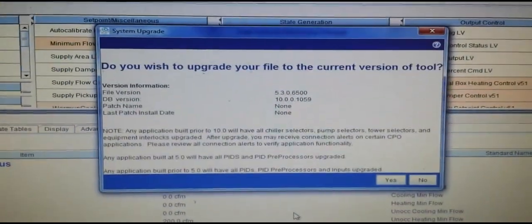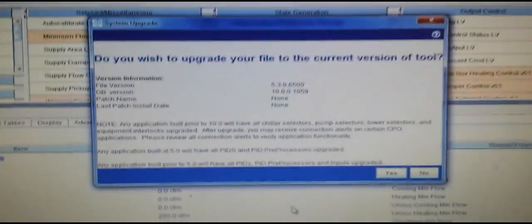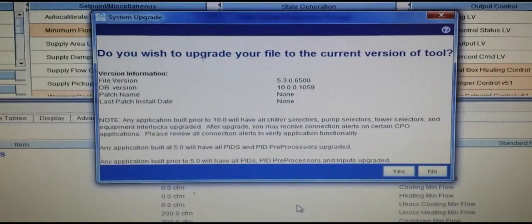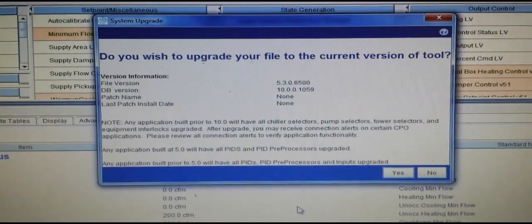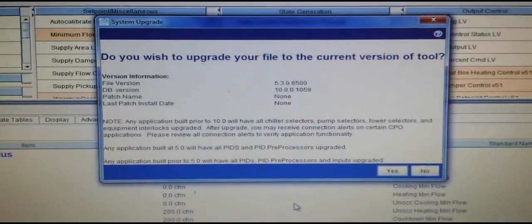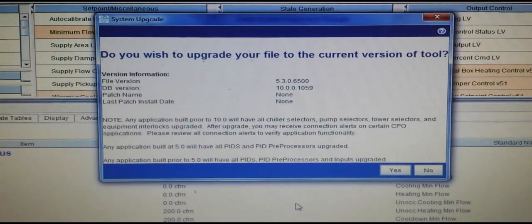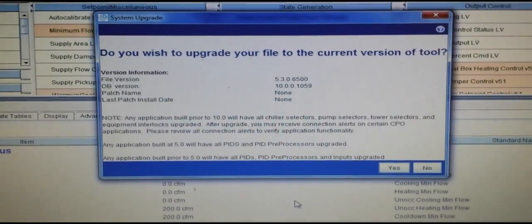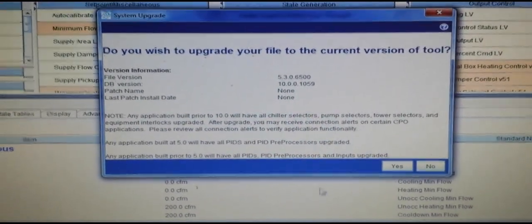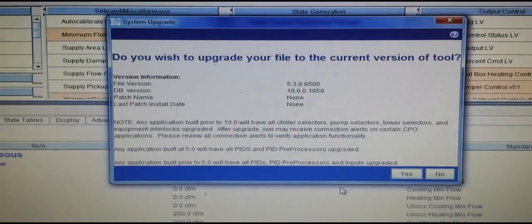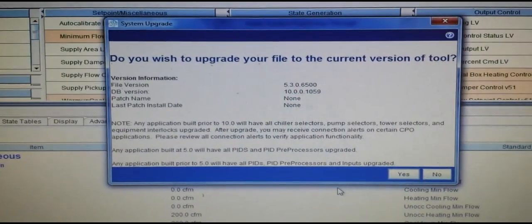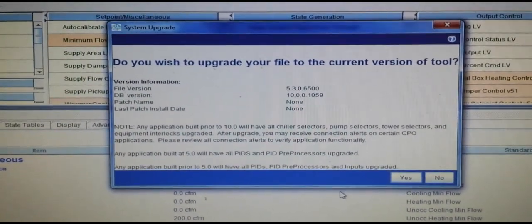If you are using a different rev level of CCT than the program for the zone controller was written with, it will ask you if you wish to upgrade the file to the newer version. In order to download this file or make the major changes that you need to make, you must upgrade or use the same rev level of CCT.